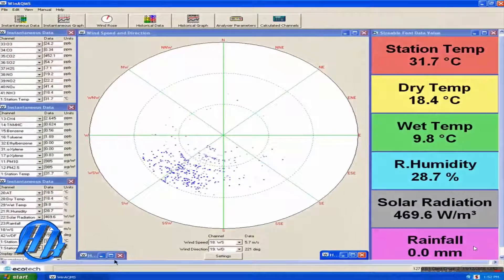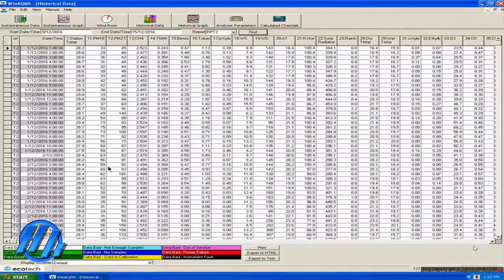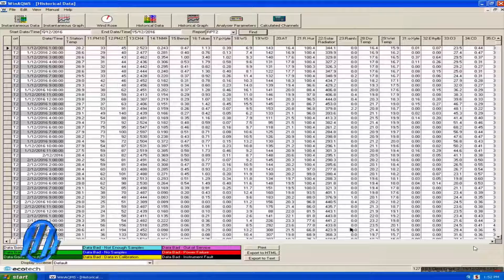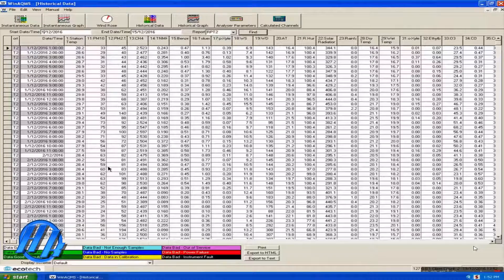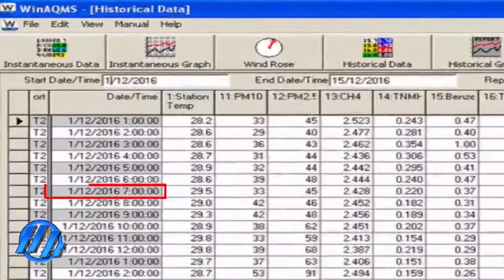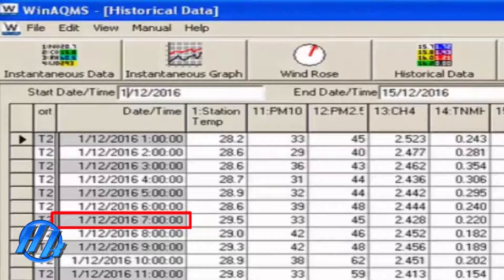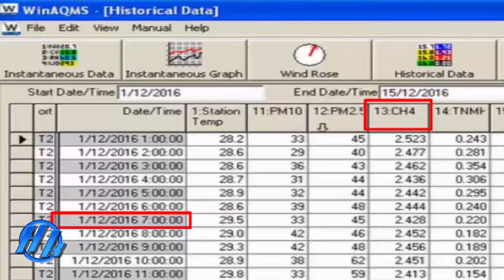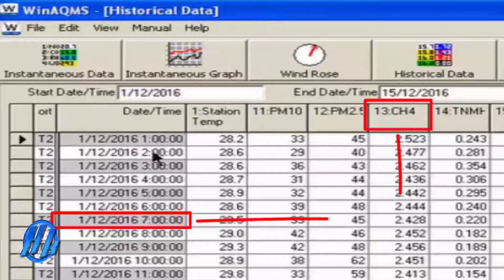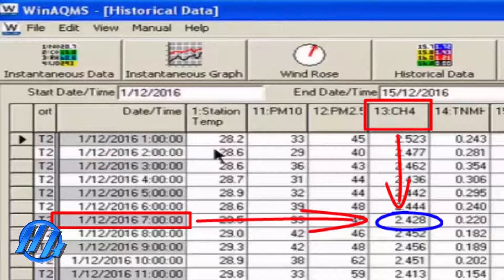The software can also retrieve old historical data from the analyzers. Here you can see a table showing the measured values for any gas at a certain date and time. For example, on December 1, 2016, at 7 o'clock in the morning, the measured value of methane gas, CH4, was 2.428 ppm.